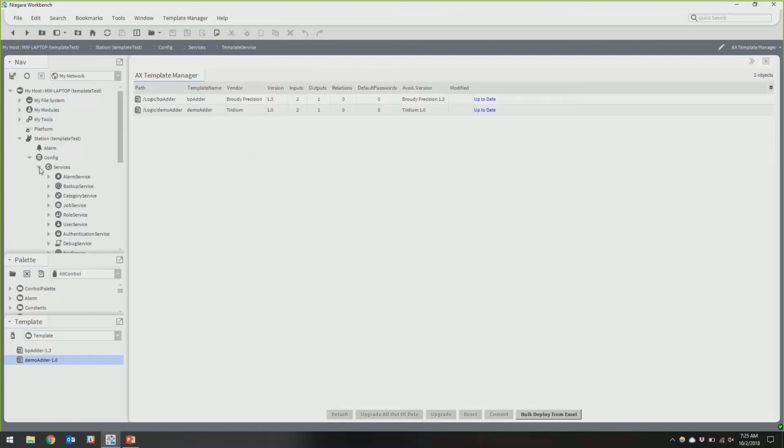I've got a standard PID loop folder that's got all the KI, KP, all those parameters already built in with the right slots, and then I've got a PX file that has a line chart with everything relativized to that folder. So anything that I change in that folder, I automatically have a tuning tool to watch the line chart and adjust set points and adjust gains and stuff.